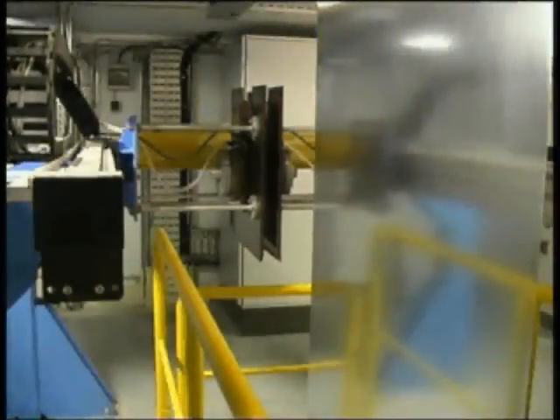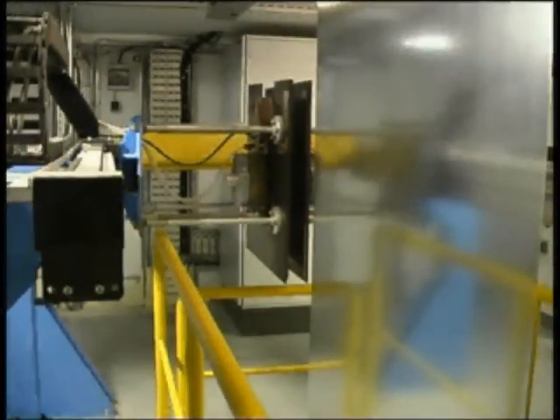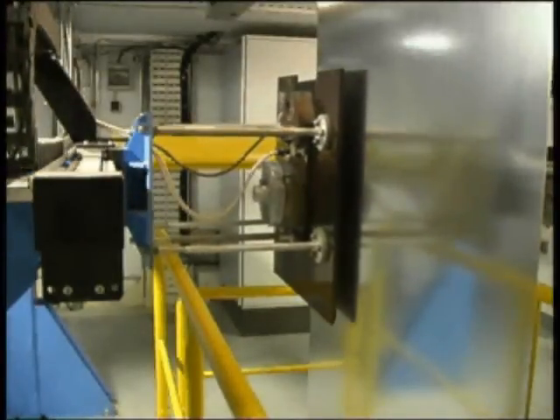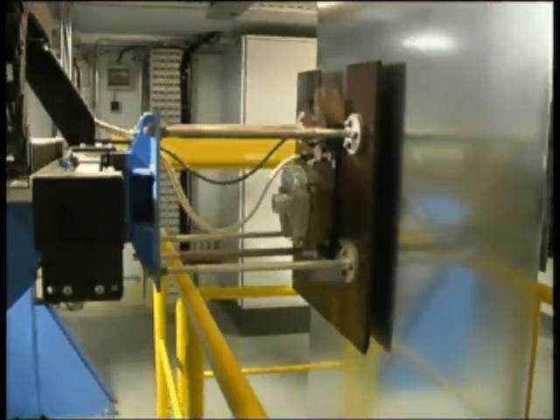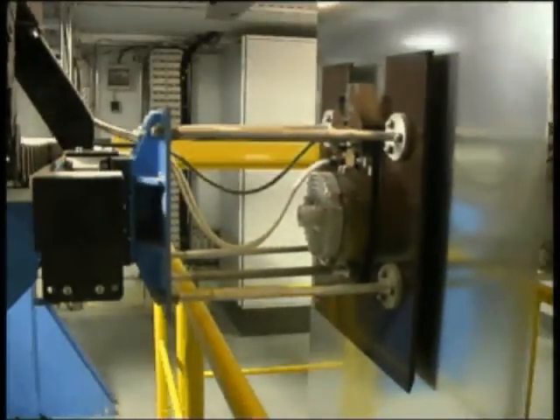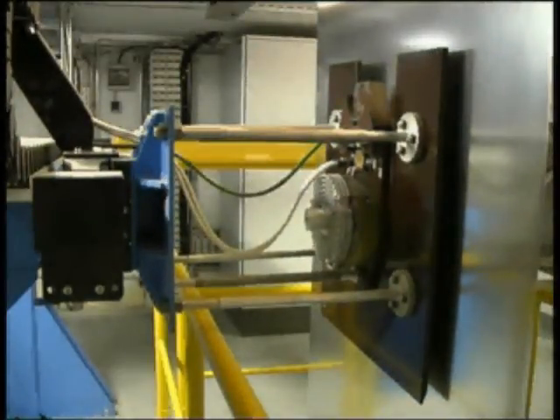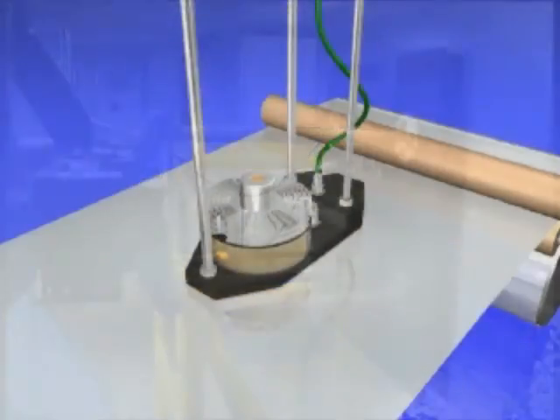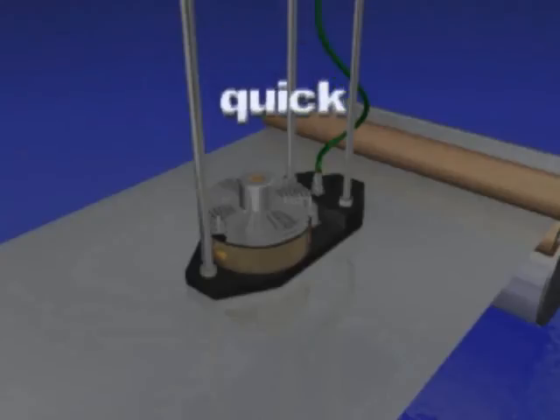The magnetic pulse induces a signal in the receiving coils and is caused by the strip movement. An electronic measuring device calculates the gradient of the residual magnetic field intensity, which is a parameter for the tensile strength and the yield point of the material to be inspected.